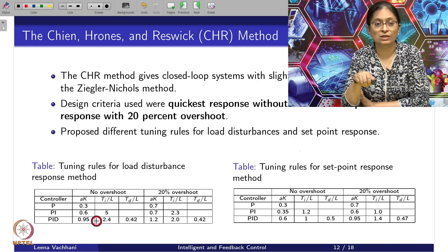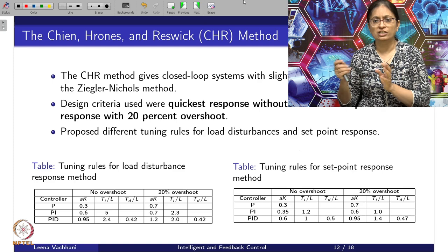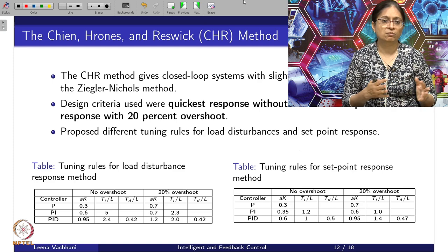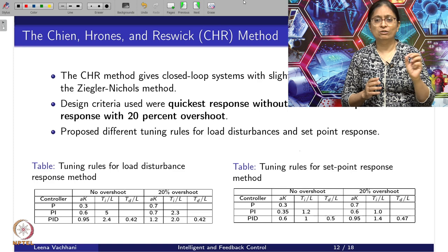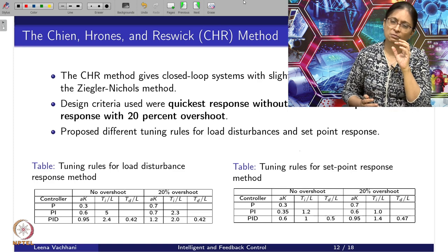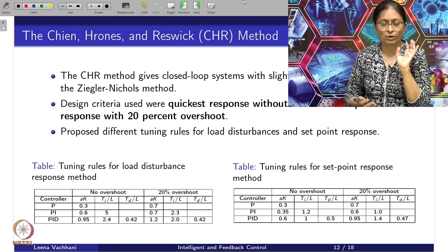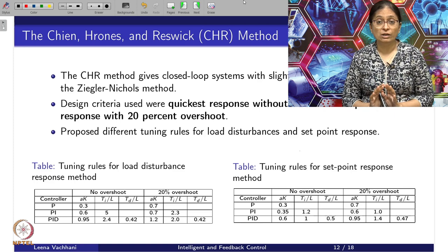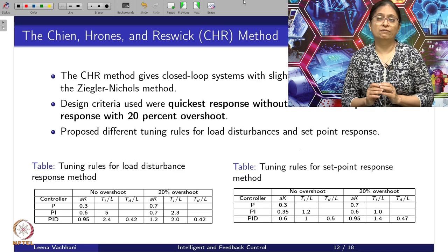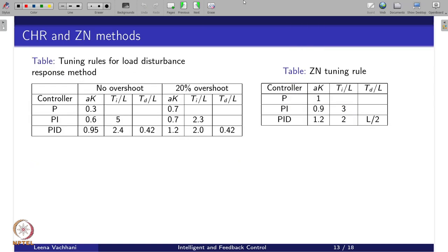As soon as you introduce integral control, you can have a better idea about what the load disturbance and set point response could be. That is where the difference comes in — you have to refer to the table for what you want: load disturbance with no overshoot, or set point response with 20 percent overshoot. Refer to the table and based on that the tuning will change. For PI or PID control, you have to decide the control objective: whether load disturbance rejection is the priority or set point regulation.